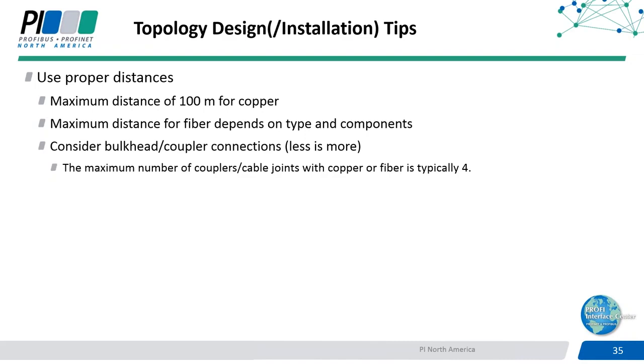I don't know how many times I've seen some electricians go out there and install some cable, and they kind of loop it in the cabinet, but they don't really know how much is out there. So you go and start looking at those cabinets, and all of a sudden you're probably over the 100 meter limit pretty quick.